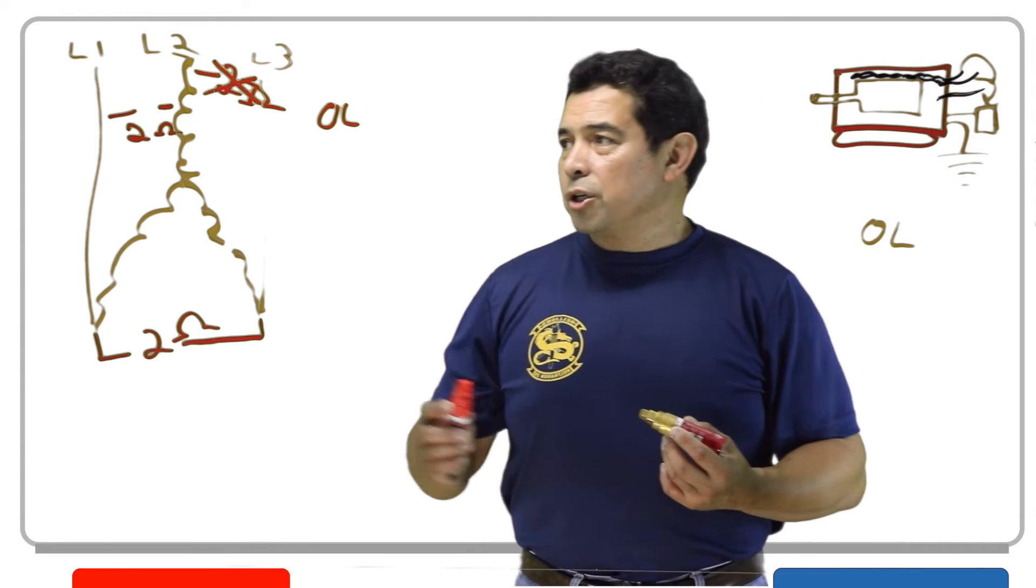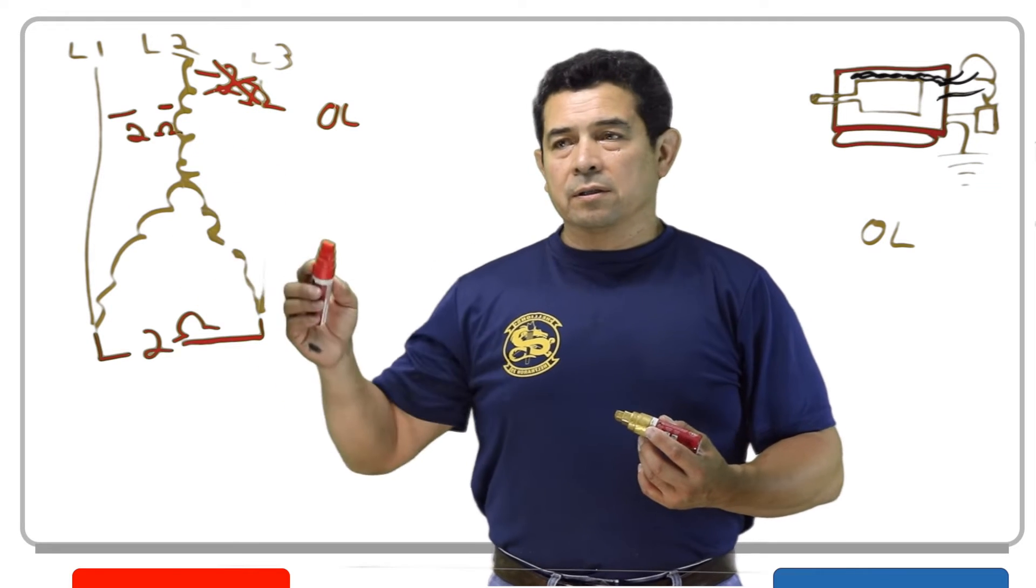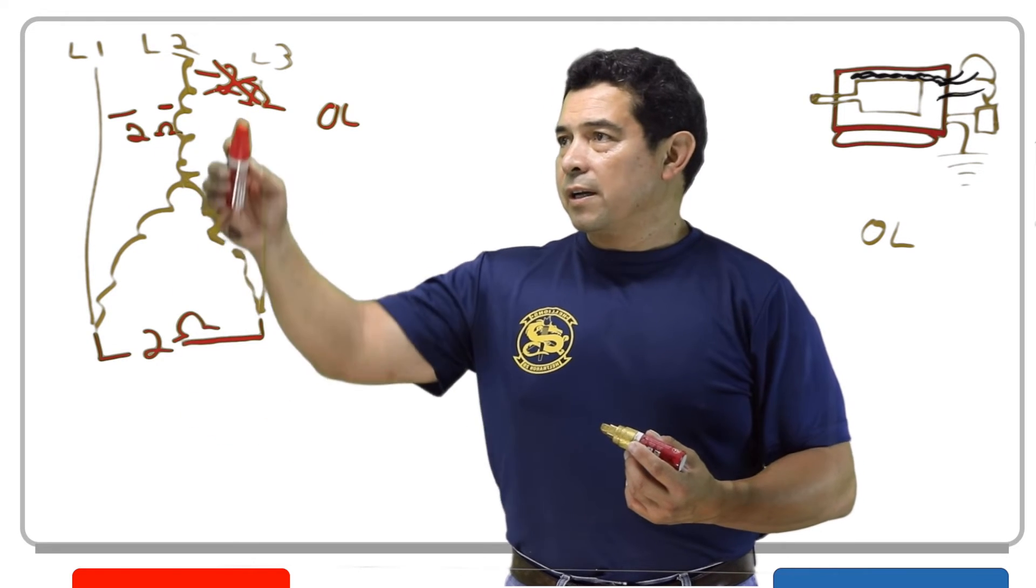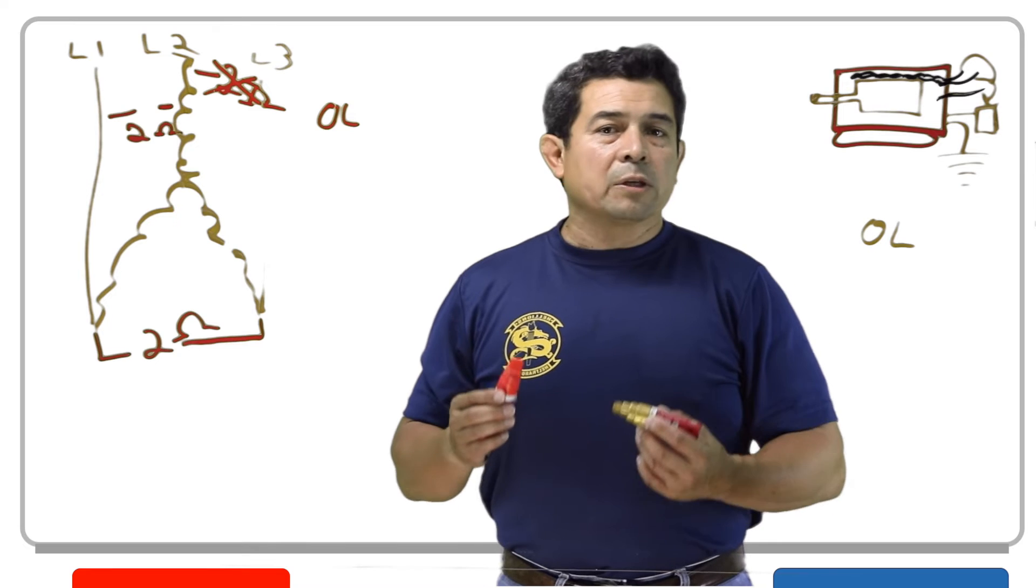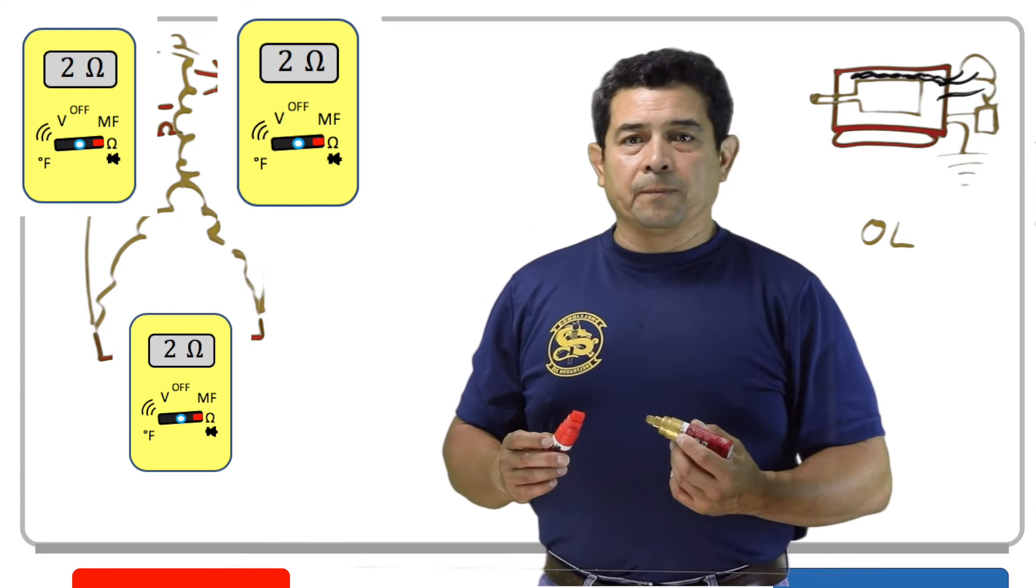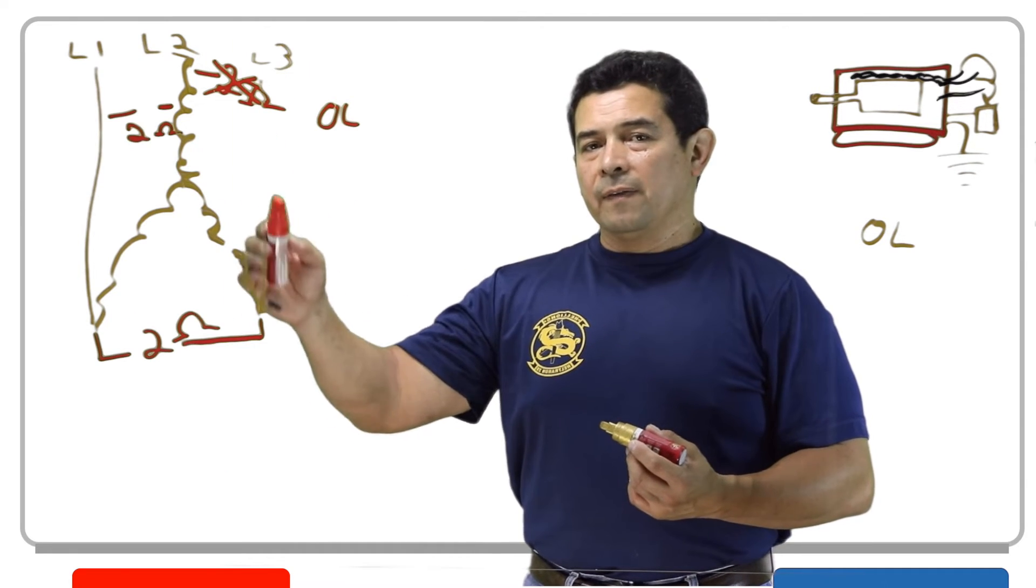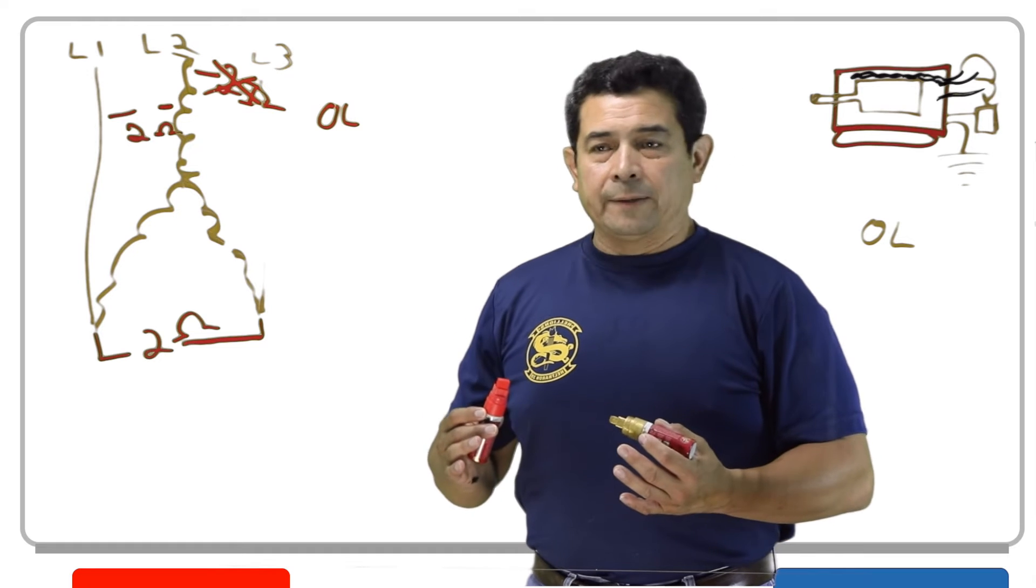Now another thing that we're going to check is the resistance on this. This is one of the first things that I do, is check the resistance, make sure that they are all the same. Now, if they're not the same, that tells me that there's a problem and that motor is just going to be bad.